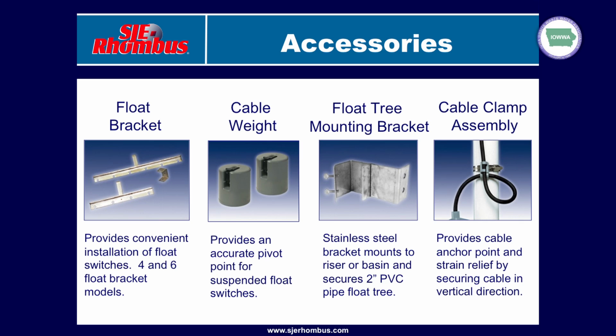Question on that last one where you're talking about, you stated either to the float tree or the discharge pipe. As the manufacturer of those floats, do you have a recommendation to do that or not do that? Because I hear a lot of counties talking about not attaching to the discharge pipe, or certain contractors saying build a float tree or get a custom built float tree. I specifically install a lot of your guys' things for our manufacturer guys, so I guess I was interested in if you have a preference. Yeah, the question was, from a manufacturing standpoint, do we have a preference for how you secure the float switches into the tank, whether it's the discharge pipe of the pump or a float tree?